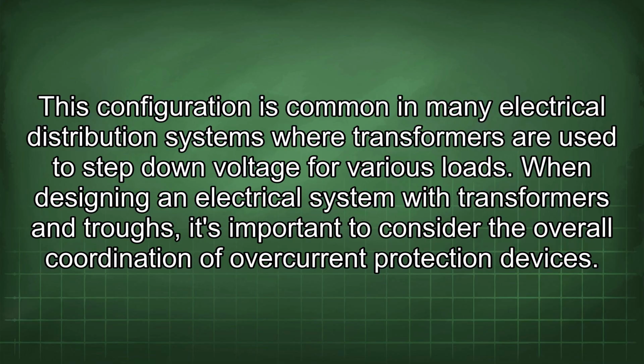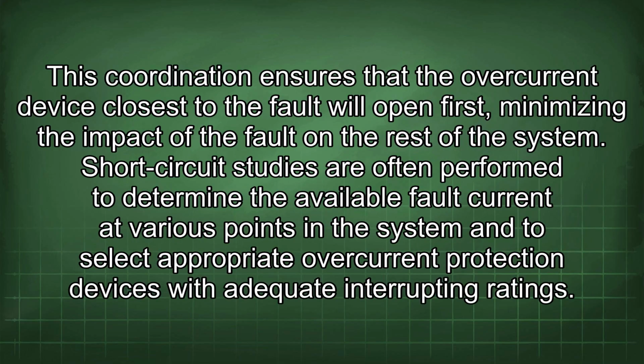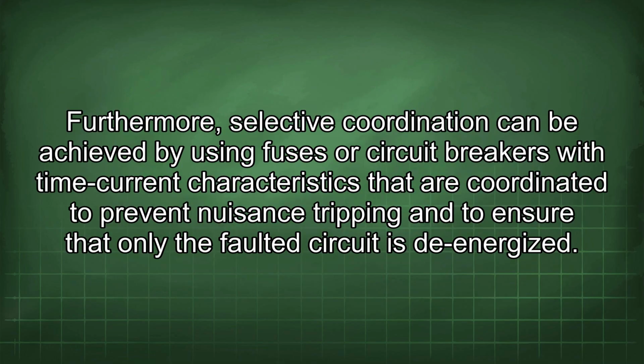When designing an electrical system with transformers and troughs, it's important to consider the overall coordination of overcurrent protection devices. This coordination ensures that the overcurrent device closest to the fault will open first, minimizing the impact of the fault on the rest of the system. Short circuit studies are often performed to determine the available fault current at various points in the system and to select appropriate overcurrent protection devices with adequate interrupting ratings. Furthermore, selective coordination can be achieved by using fuses or circuit breakers with time current characteristics that are coordinated to prevent nuisance tripping and to ensure that only the faulted circuit is de-energized.